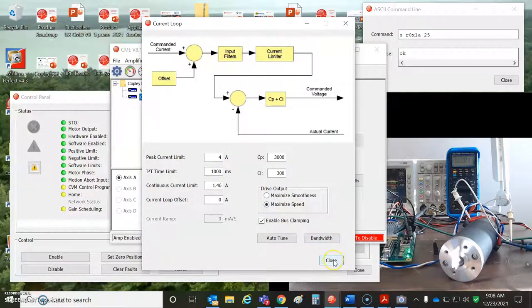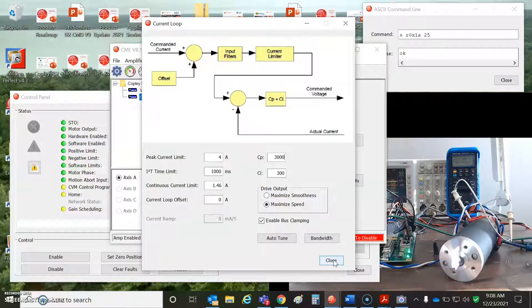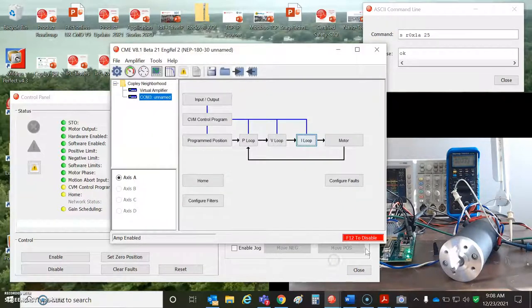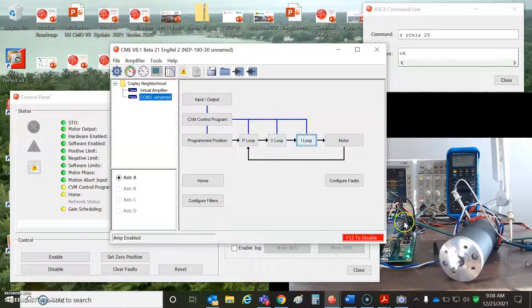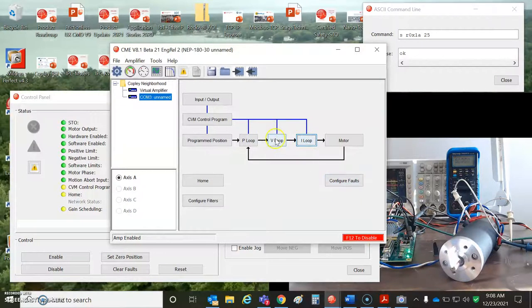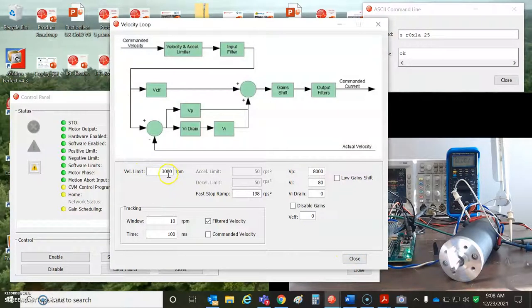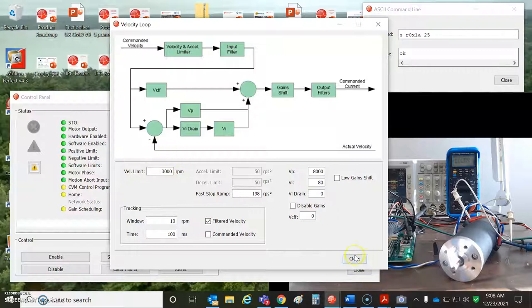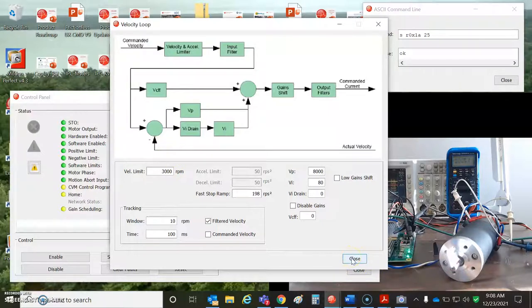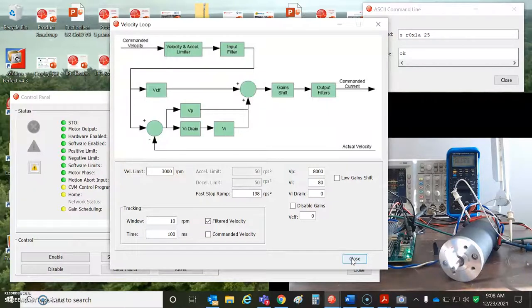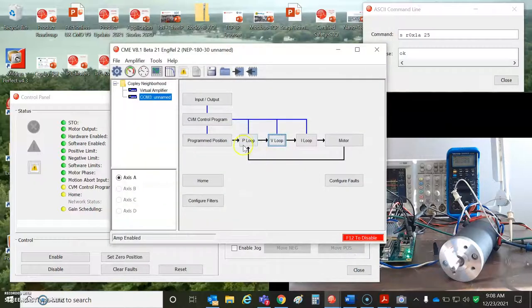I use this to phase the motor. So when I jog it forward in current, the voltage, the count should go up and the speed should go up. If it's inverted, you'll get runaway. So swap the motor wires. So you can just swap it. It's easier to swap the motor wires and the tack wires. Cause I got them soldered on there. You can tune the velocity loop, set some speed limits. That's if the tack is still connected. If it's disconnected, that's a runaway condition and you'll have to take countermeasures, some sort of position observer or voltage limit to shut down the drive.